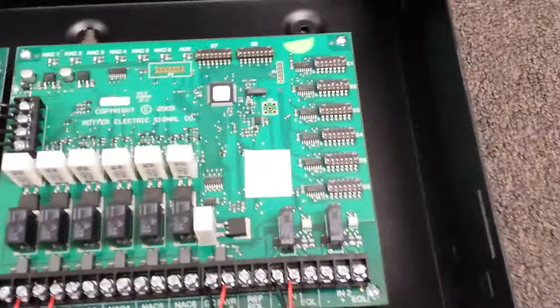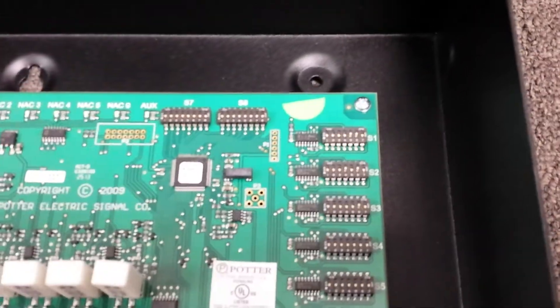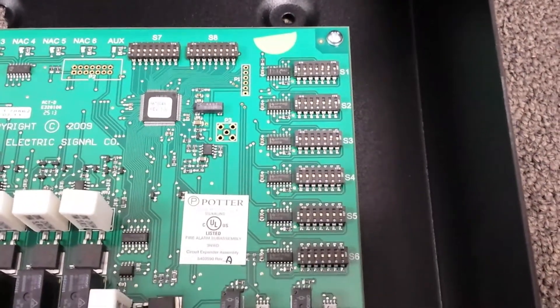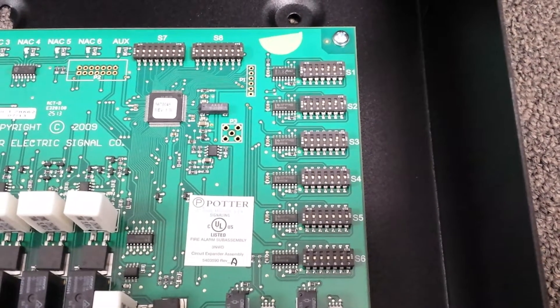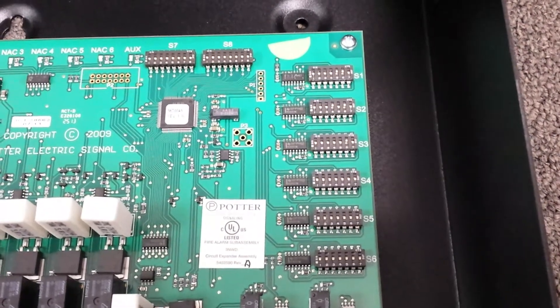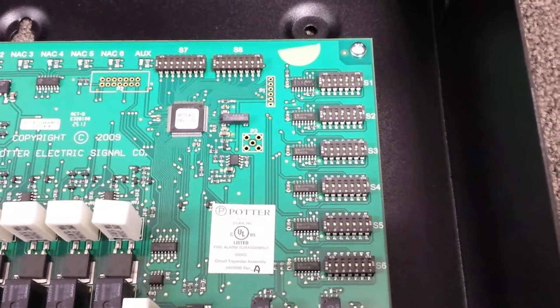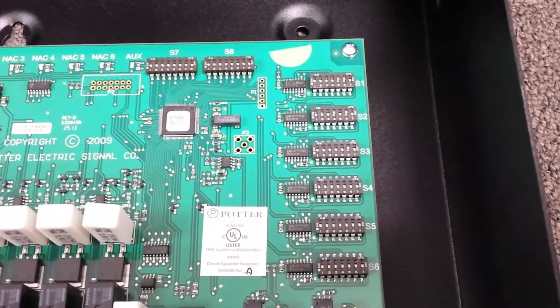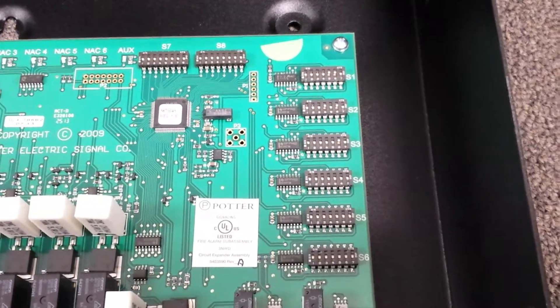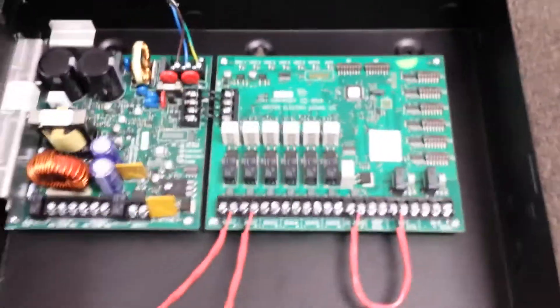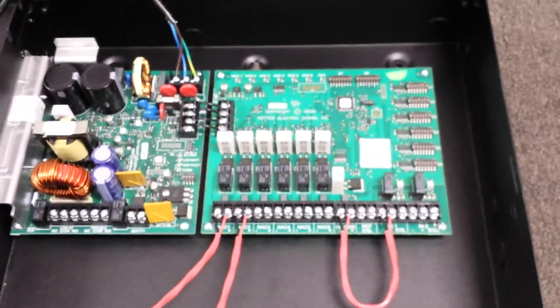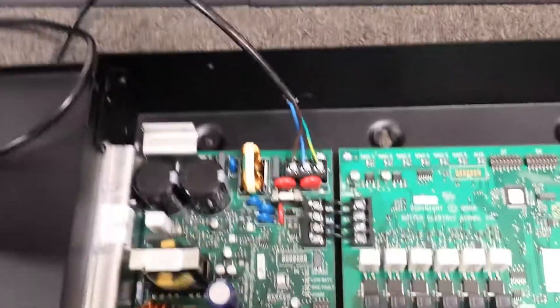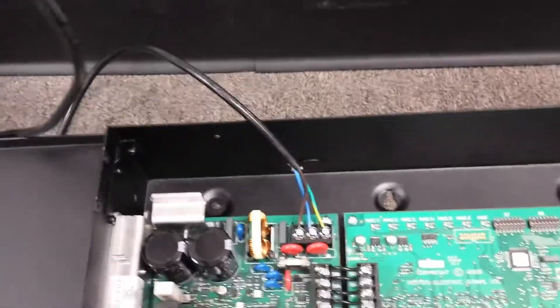Now the way you achieve all these settings is you can see here that they have individual dip switch settings for each of the six NAC outputs. So I've gone ahead and set the trigger input to constant and the switch one, S1 up there to wheel lock and S2 to system sensor. I'm not going to get too much into detail on the settings. You can find that in the manual once you play with one of these things. But I'm going to go ahead and plug it in and give it a shot.